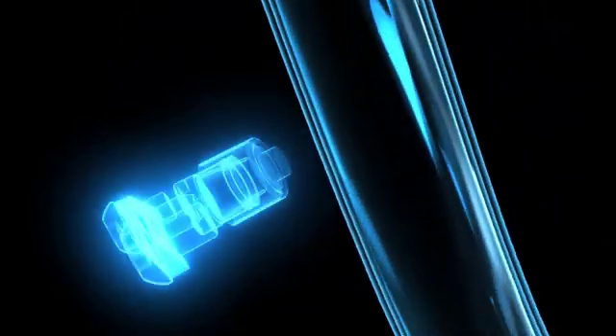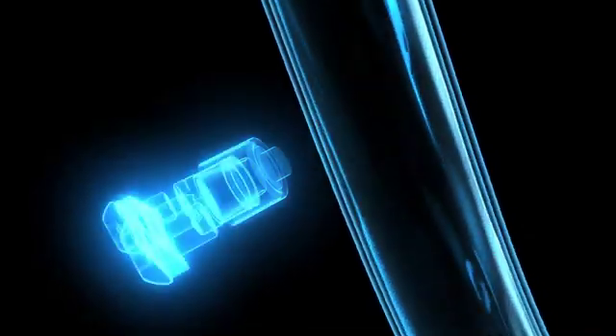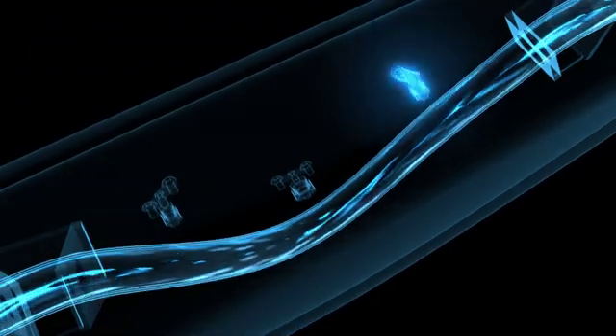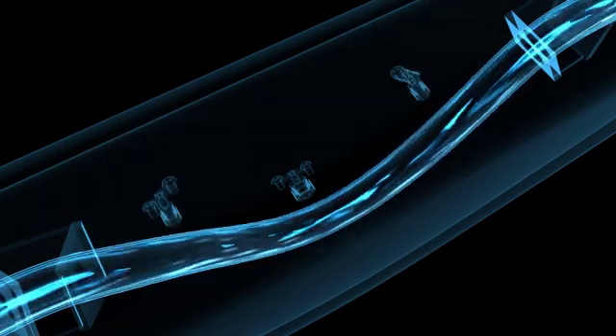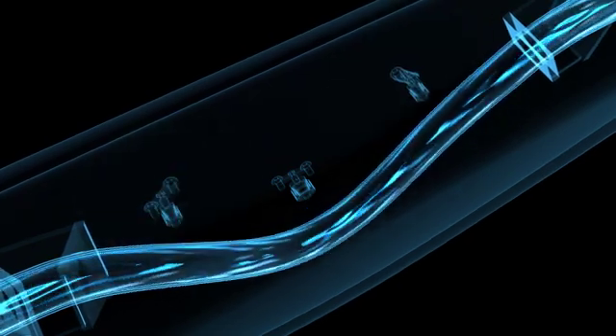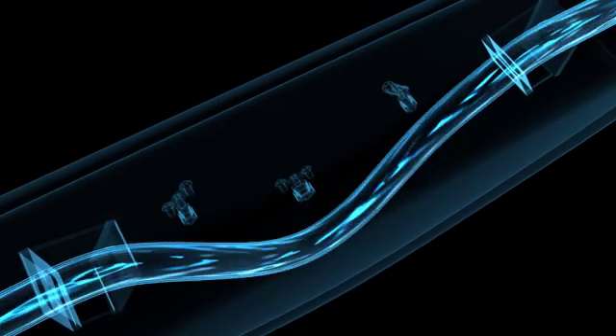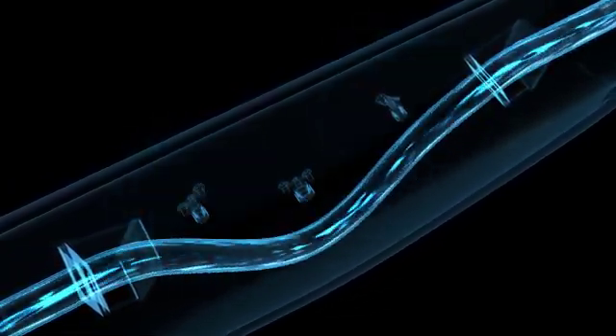The highly sensitive sensors pick up this change in the tube oscillation in terms of time and space. This is known as the phase shift and is a direct measure of how much liquid or gas is currently flowing through the pipe. The higher the flow velocity, and thus the total flow, the greater the deflection of the oscillating measuring tube.